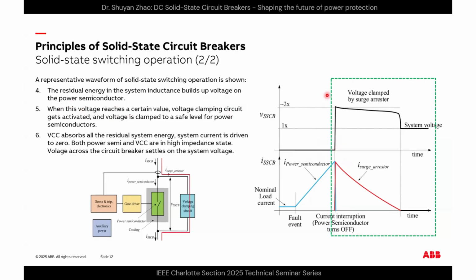When this voltage reaches a certain value here, the voltage clamping circuit, that's what it's called, right, gets activated, and the voltage is clamped to a safe level for the power semiconductors. This voltage clamping circuit absorbs all the residual system energy, so the system current is driven to zero. Both the power semiconductor and the voltage clamping circuit are in high impedance states. And then in the end, the voltage across the circuit breaker settles to the system voltage. Also, the system current is practically zero in the end. That's how a solid state circuit breaker cuts off a fault in a system.